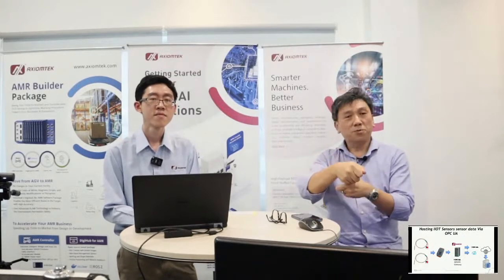Another important thing about OPC is that in a process plant, you're usually driven by PLC controllers or transmitters, process controllers. Each of these has their own set of protocols - for example Siemens has their protocol, Omron has their own, Allen Bradley has their own, Modbus has Modbus. Nobody has the same unified thing.